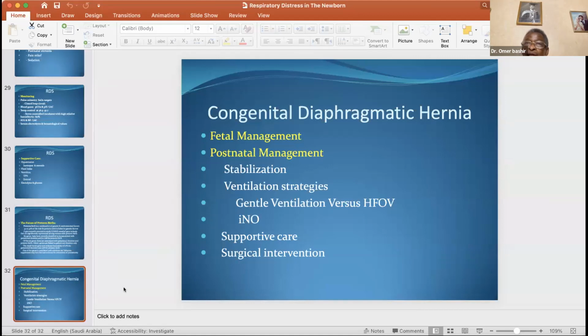The good thing about volume guarantee is that you set a volume according to the requirement. For very small babies, you probably require about 4 to 5 ml per kg. For bigger babies, you probably use about 3 to 3.5 up to 4 ml per kg. And that volume needs to be delivered by a certain pressure. So you stay with the ventilator, see how much pressure is required to deliver that volume. It is important to look at the PIP and the mean airway pressure. In fact, this is a good way of weaning those babies. When the mean airway pressure in a volume guarantee ventilation drops to about 7 or 8, that tells you that the baby is ready to come out of the ventilator.